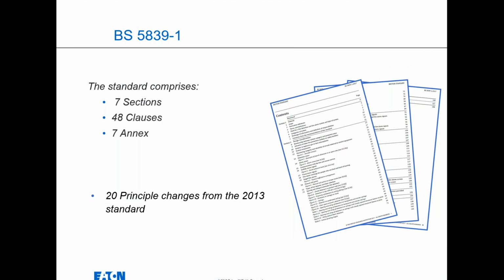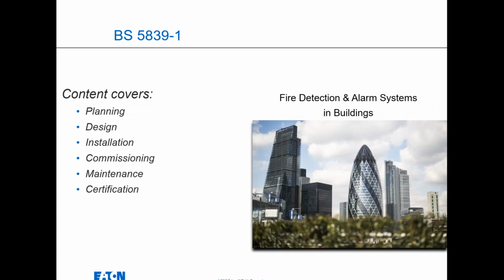So the standard is 7 sections, 48 clauses, 7 annexes, and there are 20 principal changes from 2013 if you are familiar with 2013. So the content covers the planning, the design, the install, commissioning, and maintenance, and then the certification. And that's quite important, because as you do all this, there are certifications for design, install, commissioning, and maintenance. And those certificates should be in place in a fire binder or fire log within the premises of the building.